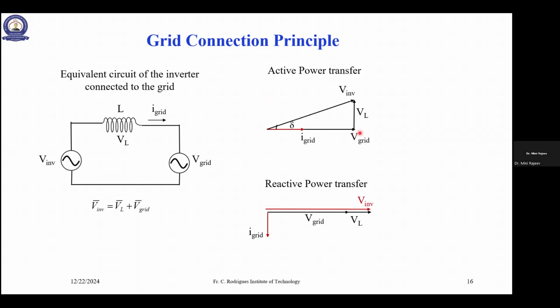That is how I am drawing it here and finding the resultant. So this is my inverter voltage. What do you understand from this? For active power transfer, there should be some phase difference between the grid voltage and the inverter voltage. So the control strategy should be such that there is a small phase angle difference between the inverter voltage and grid voltage for active power transfer when you connect PV to the grid.